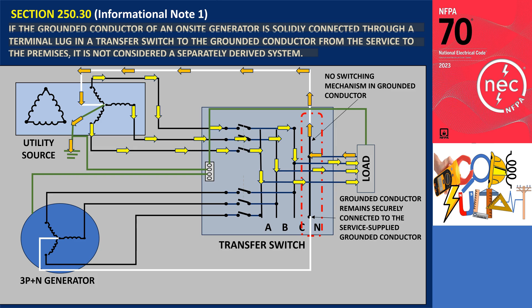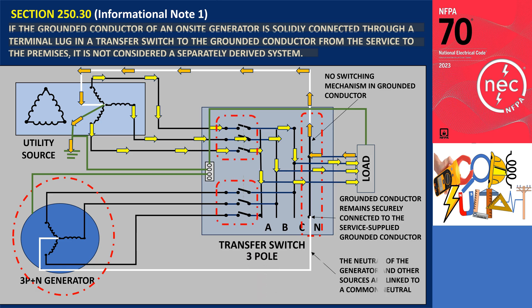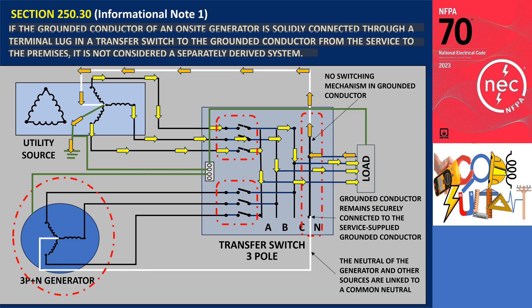This means in the case of a generator configured with three poles plus neutral, if the transfer switch utilized comprises only three poles, the neutral of the generator and other sources are linked to a common neutral. The neutral conductor is firmly interconnected to a grounded neutral conductor supplied by the service system. If the neutral of this generator were bonded to the frame and connected to the grounding system of the premises, an objectionable current would flow to the neutral conductor of the generator. That bonding point is prohibited by section 250.24. If only three poles are utilized, the generator is not classified as a separately derived system.